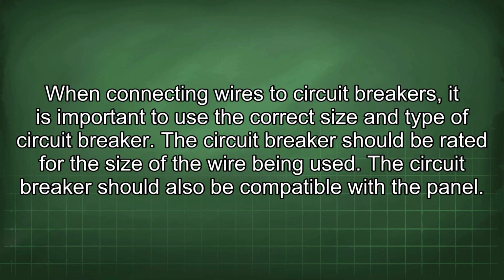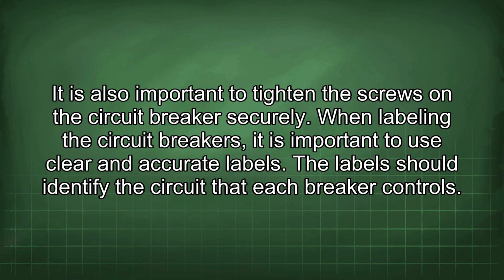When connecting wires to circuit breakers, it is important to use the correct size and type of circuit breaker. The circuit breaker should be rated for the size of the wire being used. The circuit breaker should also be compatible with the panel. It is also important to tighten the screws in the circuit breaker securely.